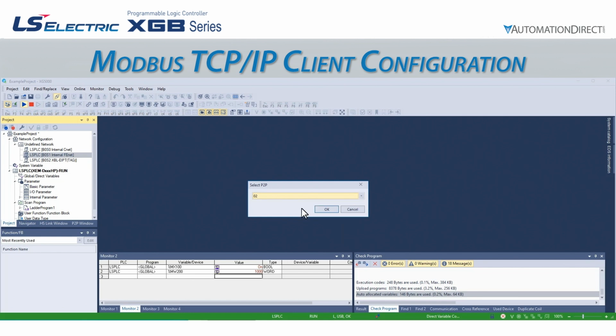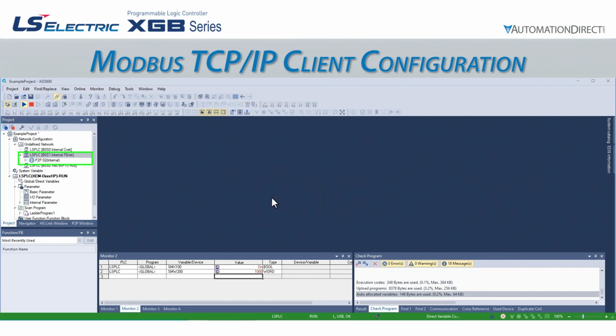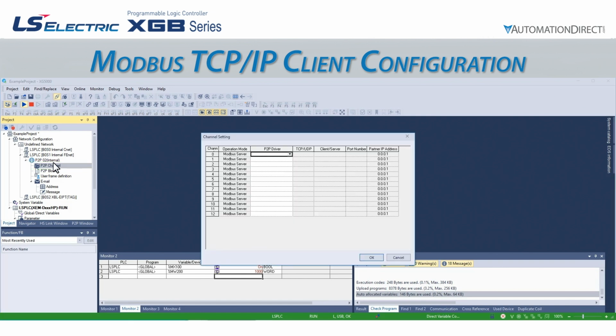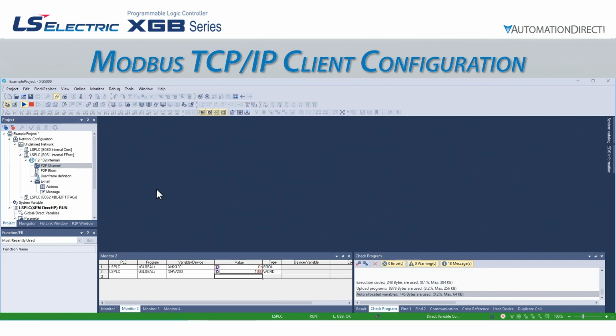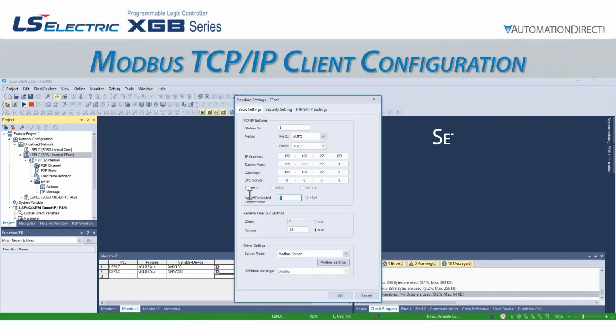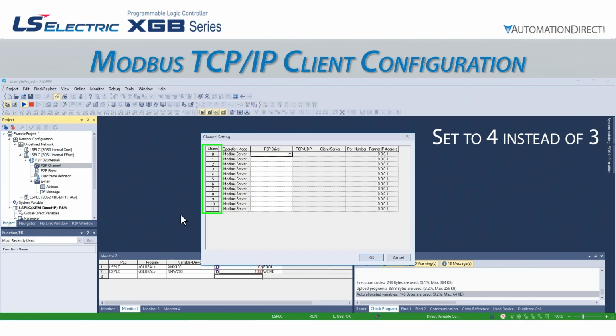Once we select our connection and click OK, we see a new peer-to-peer connection added under the internal FENet network subheading. We can now set up our Modbus client connections. We double-click on P2P channel, and the channel setting pop-up window opens. We see there are 13 connections available, numbered 0 to 12. If we had put a number other than 3 into the number of dedicated connections, we would see the number available here adjusted accordingly.